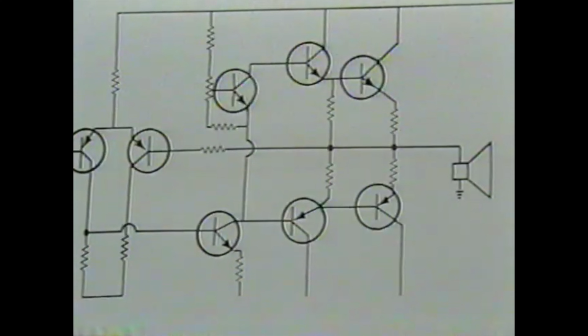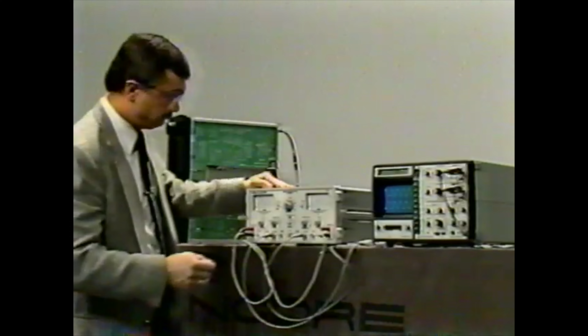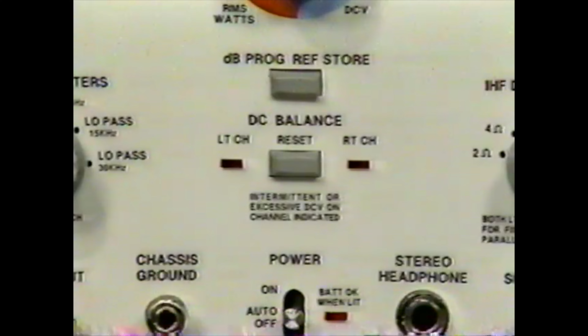Robert, take a look at these two lights on the PA81. They are part of an innovative DC balance test circuit. The PA81 constantly monitors both dummy loads for a DC offset. If either shows more than 1 volt, the light comes on to tell you which channel failed. The internal dummy load is immediately disconnected until you manually reset the circuit by pressing this button.